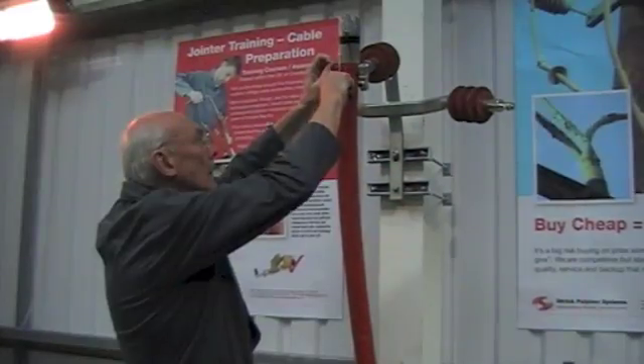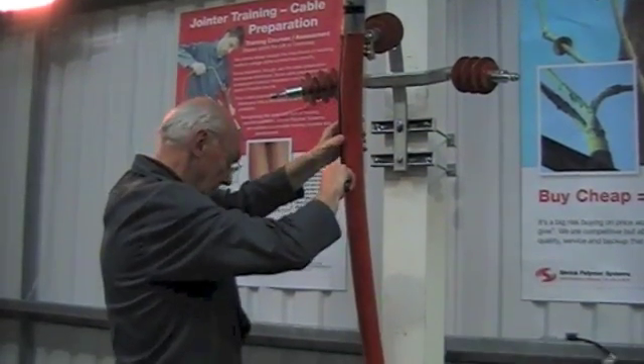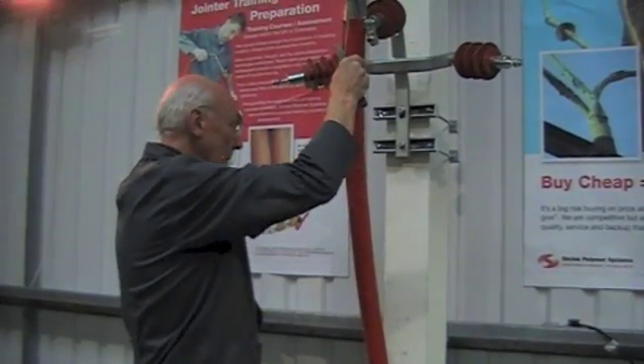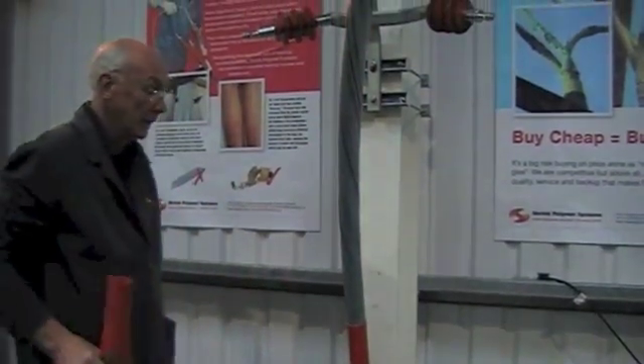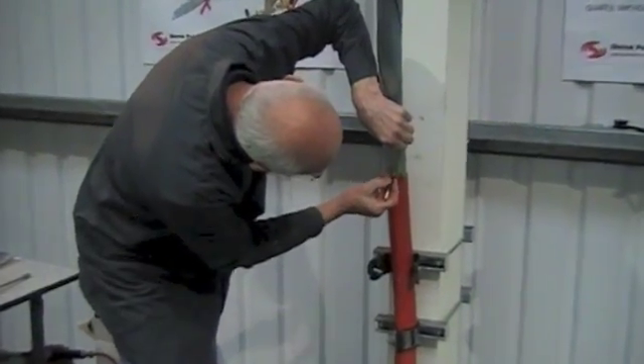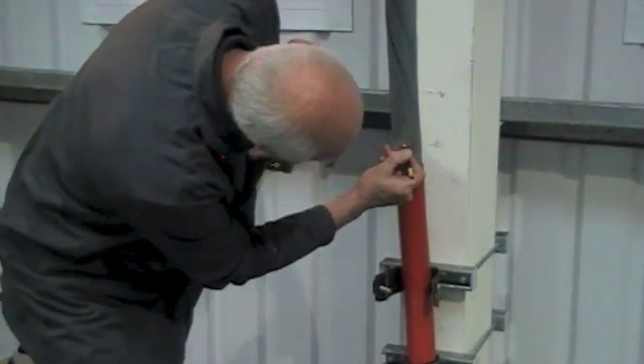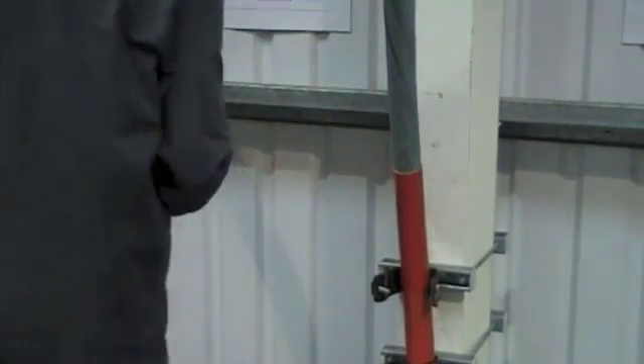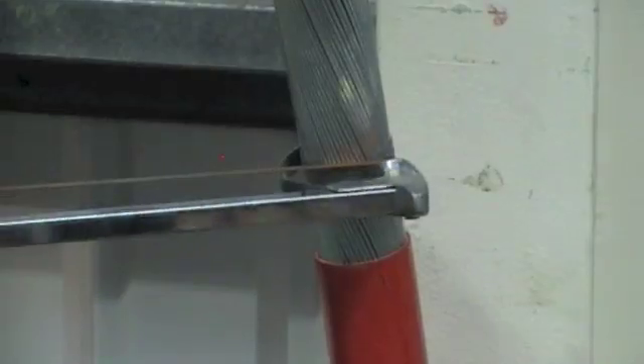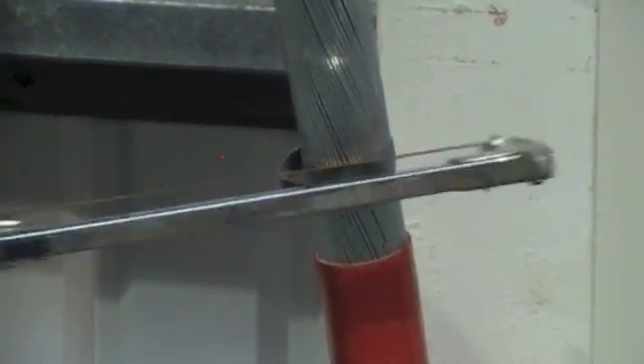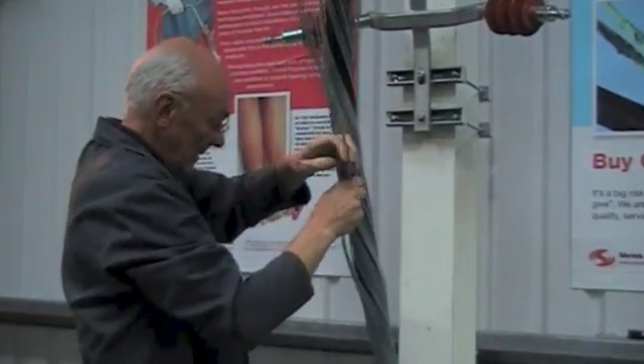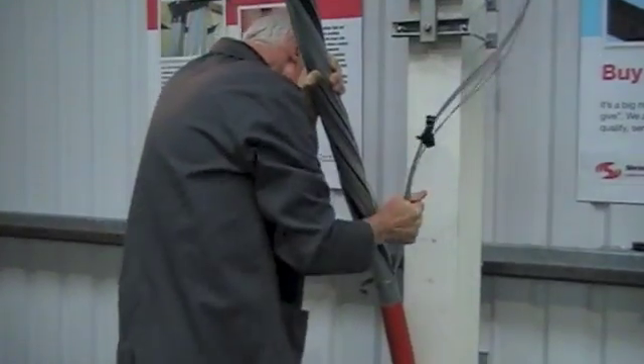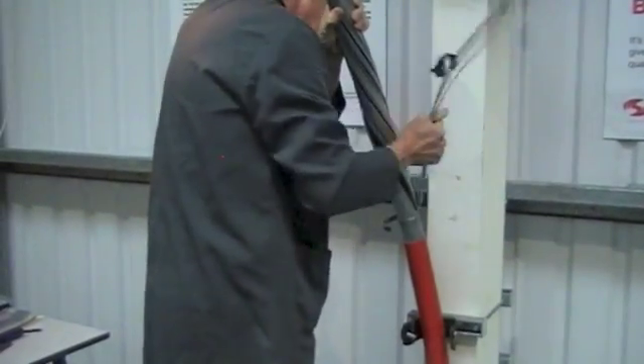Heating up the outer cable jacket will assist in removing. And here we're going to show outdoor armor earthing also. So we're exposing the armors to a dimension according to the instruction sheet for the Armor Earth Kit. After scoring the armor wires, bend back and remove.